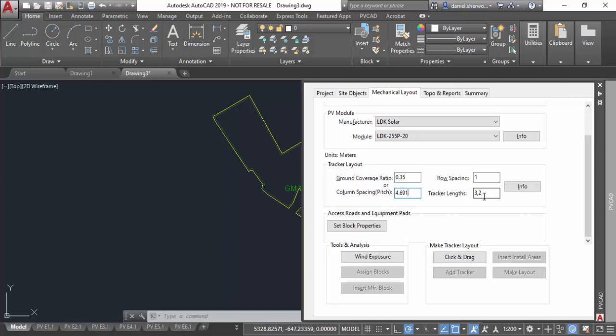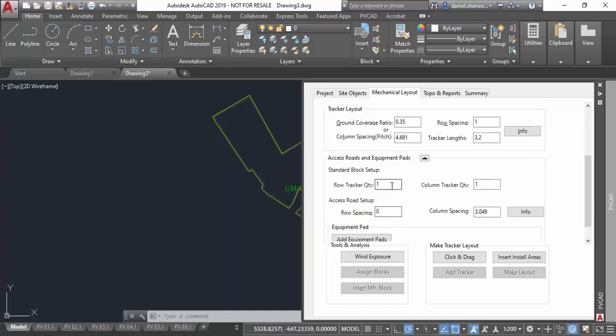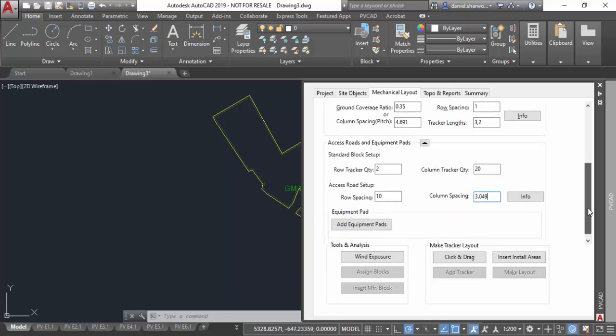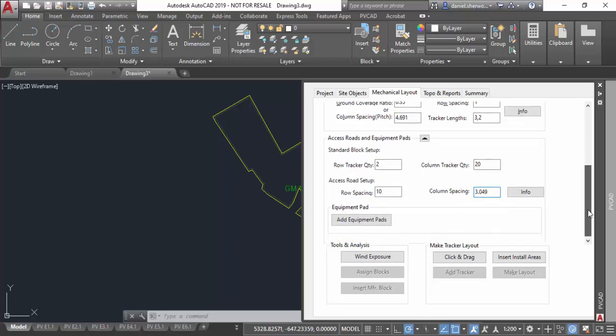Next, in utility scale mode I have the option of defining access roads between standard blocks. If I click on this button it loads up another section of user interface where I can specify a standard block of two trackers up by say ten trackers across. And then I can define the width of any access roads around those standard blocks. I'm going to put in a 10-meter access road going east to west. The column spacing by default will give you an access road that will basically leave no extra space—it'll just be equal to the pitch of the trackers. But you can override it if I want the 10-meter access road or not. I can just leave it by default for now.